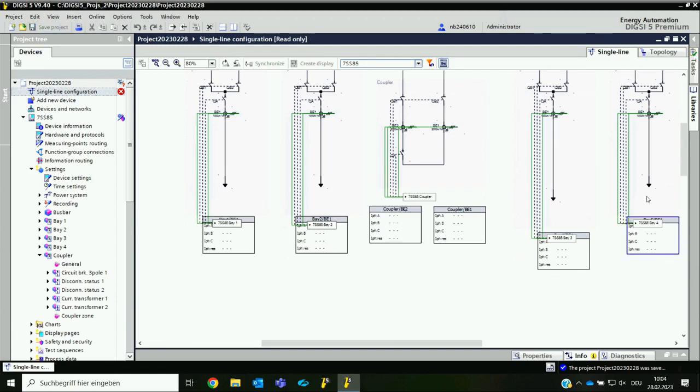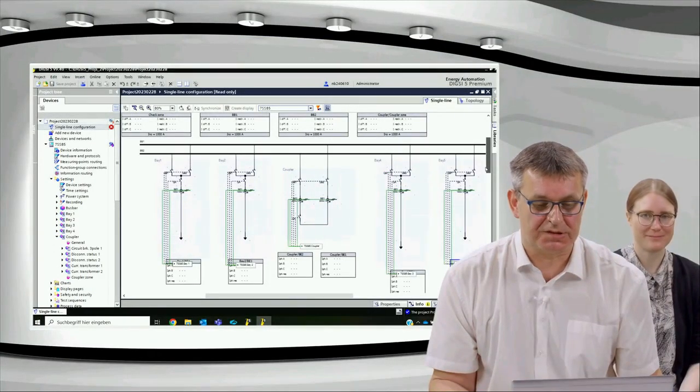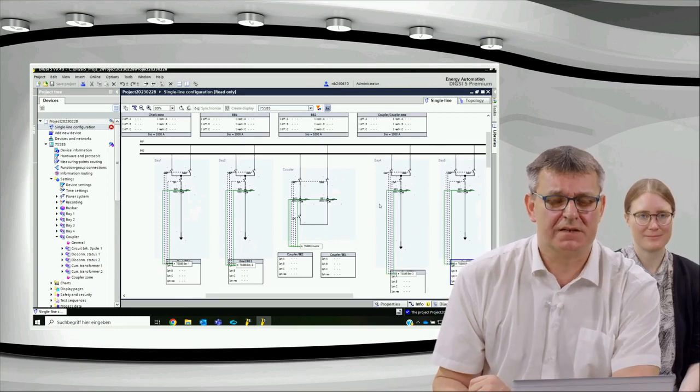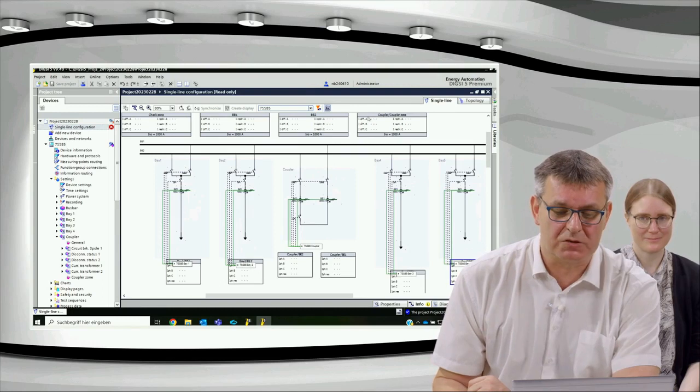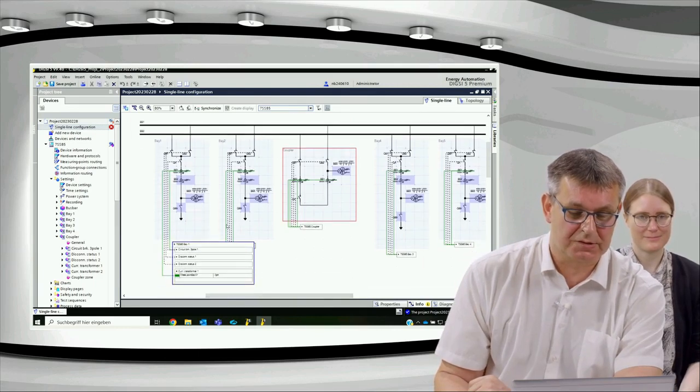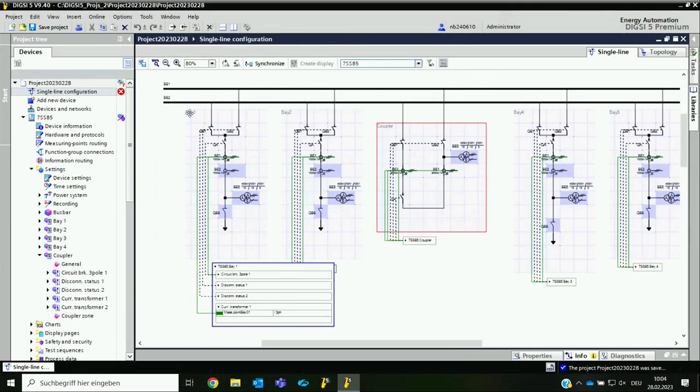Okay. That's the arrangement of the measurement boxes and the very valuable filtered view, also to check whether your configuration is right. Let me have a look at what I still want to do. Okay, I want to synchronize. I will close. If you see here, for example, the disconnector names, that's called bay 0. I guess in your project you want to name them bay 01 and bay 02. Yes, I think we have this done. Bay 0, it should be exactly project.